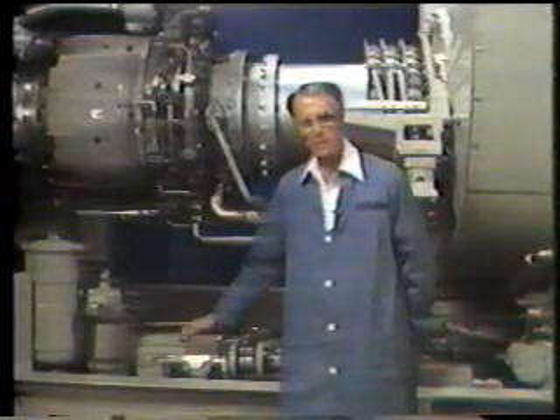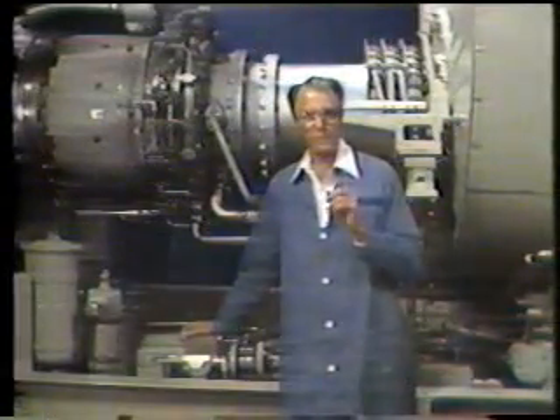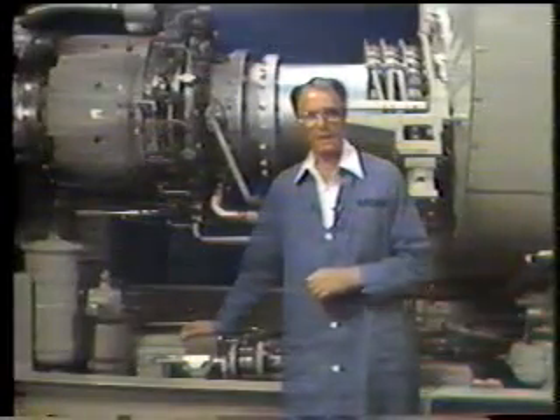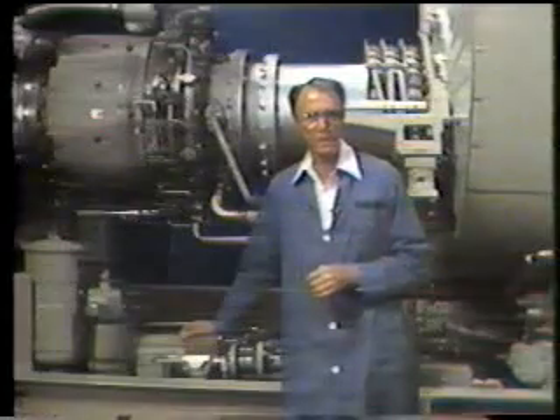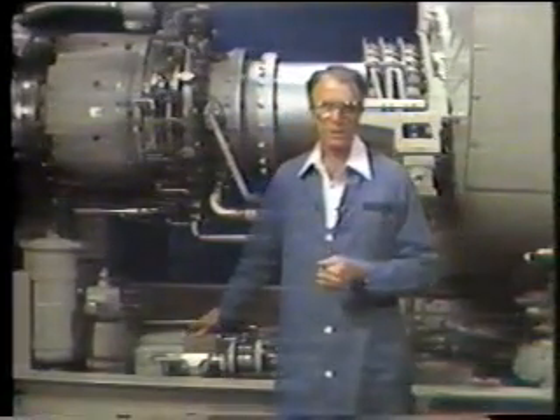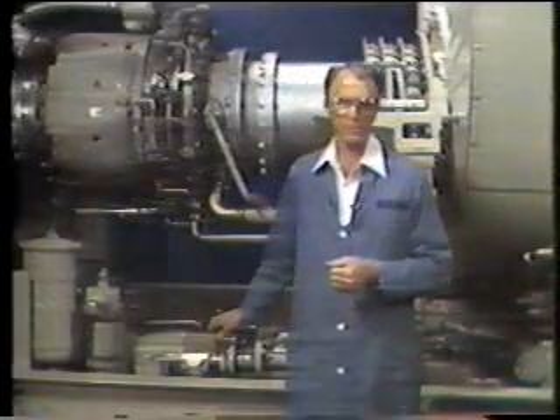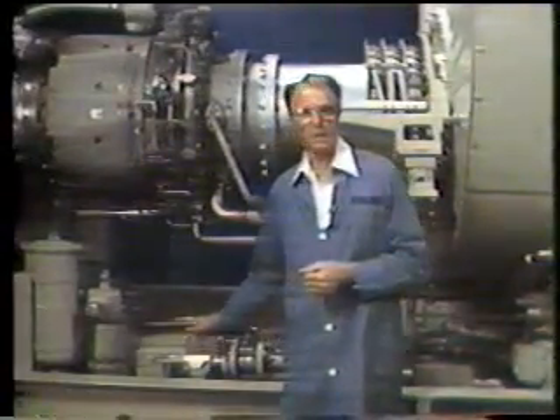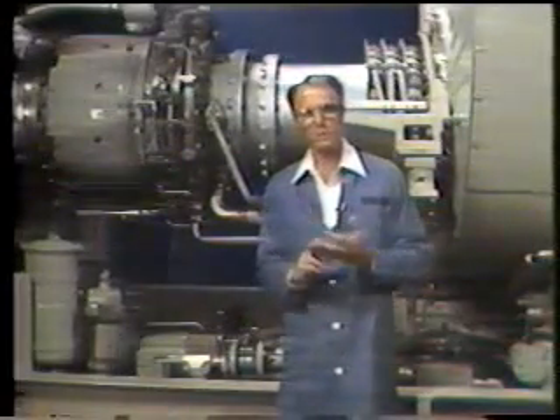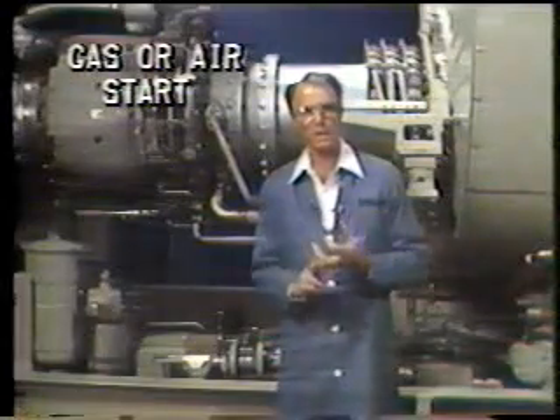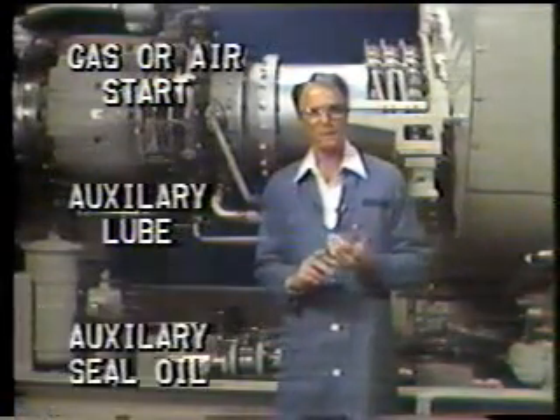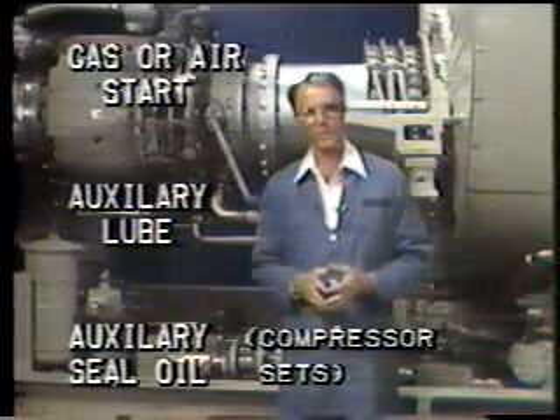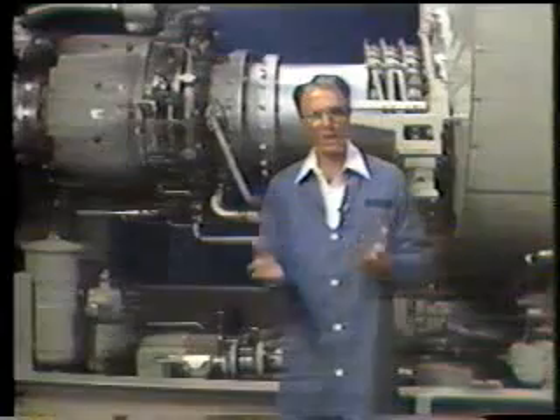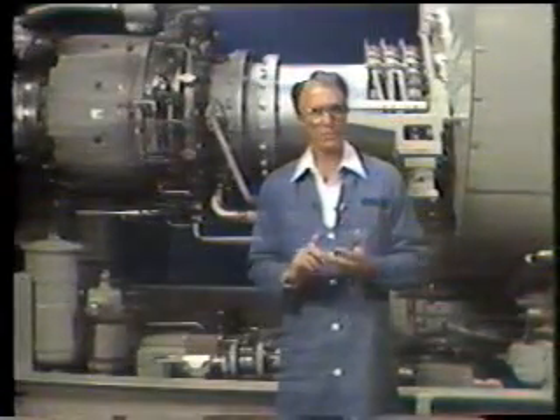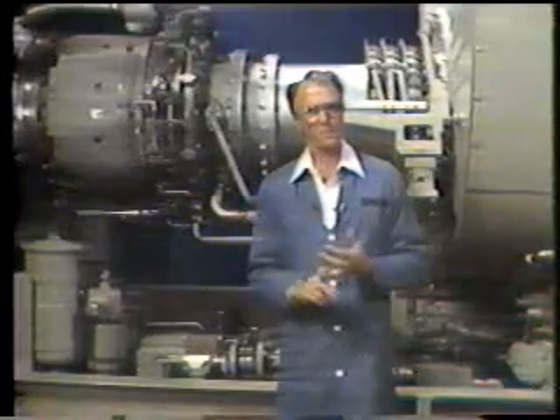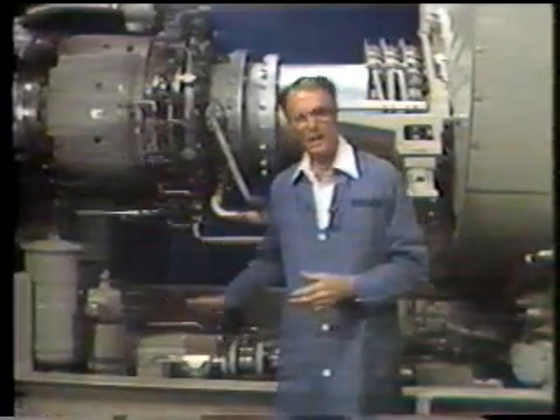Maintenance of the primary fuel shutoff valve may be required at more frequent intervals than 4,000 hours. Maintenance is required when the valve indicates even the slightest inclination to stick, or if a gas fuel valve fail shutdown occurs during startup, and as part of the intermediate inspection. The primary fuel shutoff valve, or Versa valve, is also used as the shutoff valve for the gas or air start, auxiliary lube, and auxiliary seal oil systems on Solar equipment. Now, with the exceptions of locations, system pressure source, and removal and replacement considerations, the inspection procedures are the same for the valve in all applications.